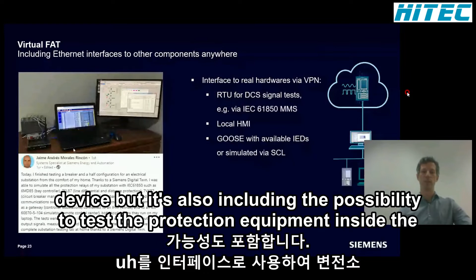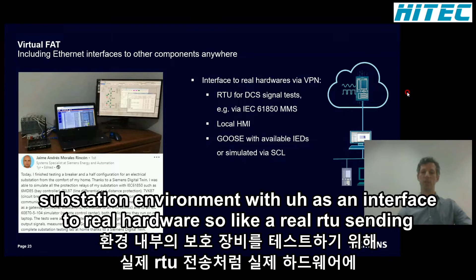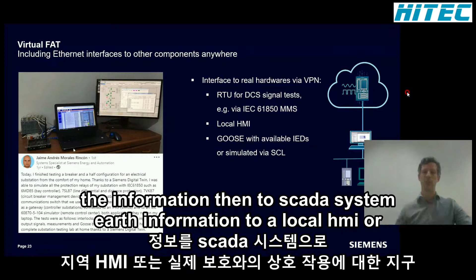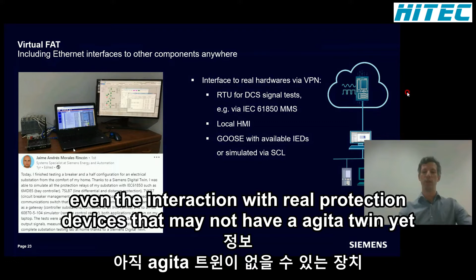The virtual factory acceptance test doesn't end with simulating one or multiple protection devices, but also includes the possibility to test the protection equipment inside the substation environment with an interface to real hardware, like a real RTU sending information to a SCADA system or to a local HMI, or even interacting with real protection devices that may not have a digital twin yet.